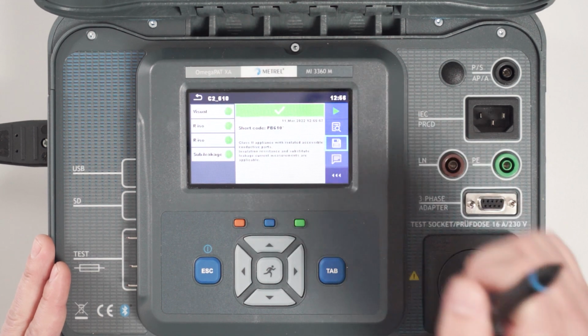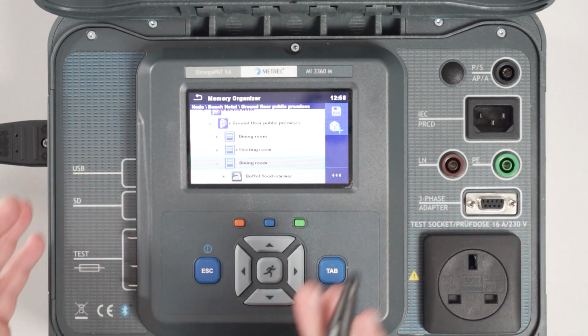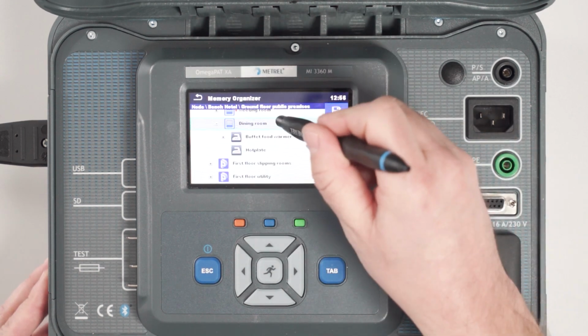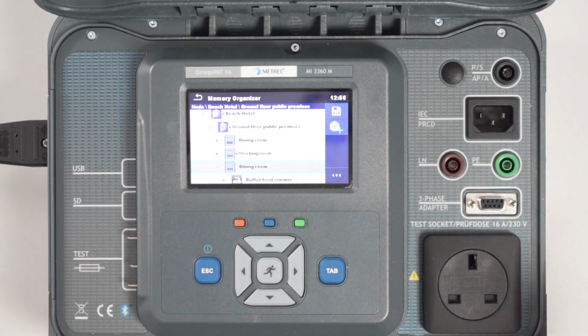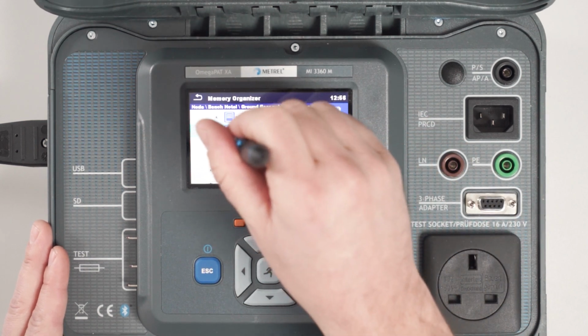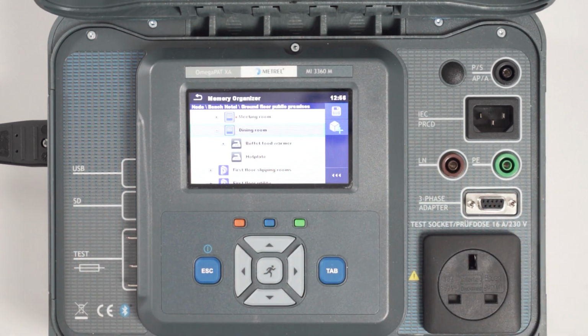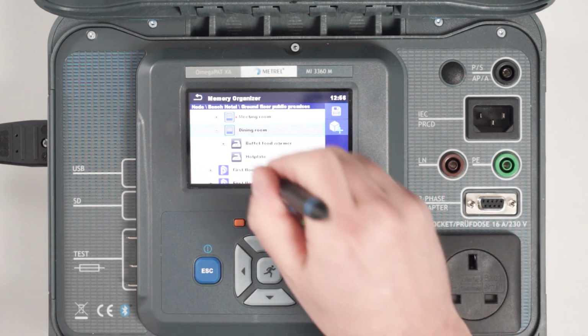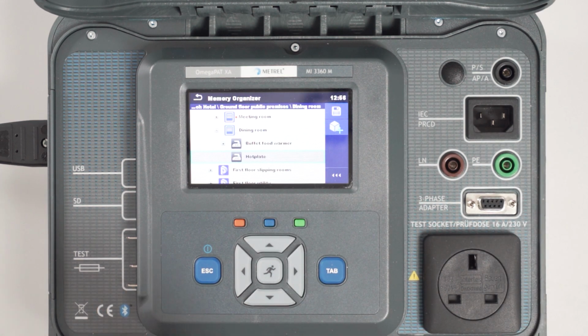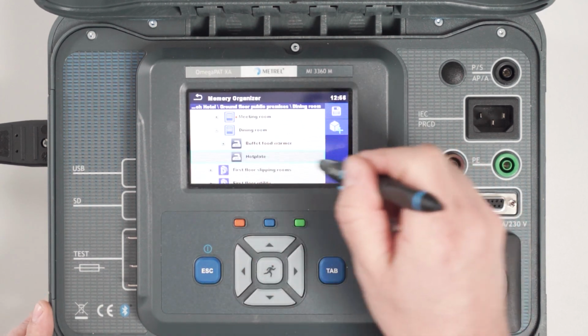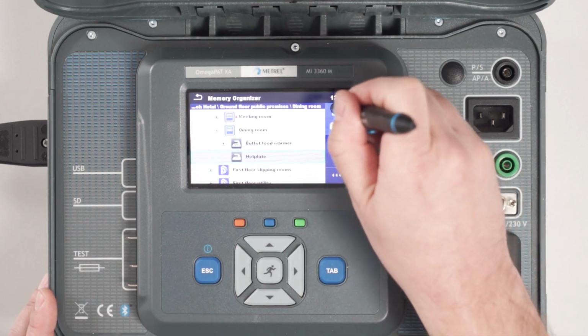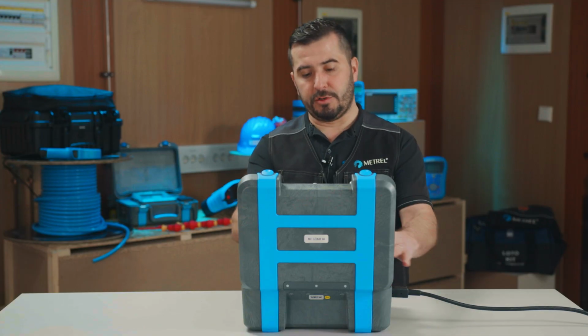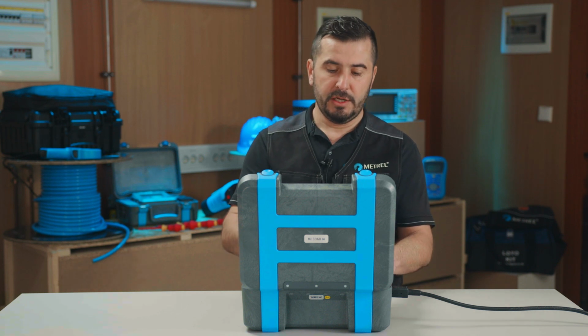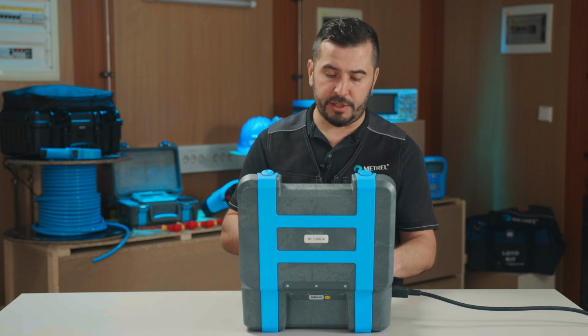Then we simply press save, and the instrument jumps into the memory organizer menu. Now the logic is a bit different from before, where we first selected the appliance and then added the auto sequence or single measurements. Here we have already executed the auto sequence itself, and now we select to which appliance these auto sequence results will be dedicated. So we select here hot plate and press save. This means that the results of this auto sequence are now securely stored inside our memory organizer.